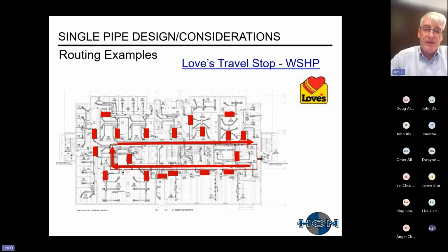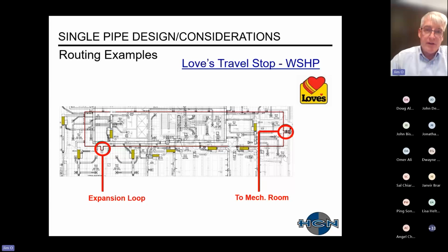On the right is a mechanical room, and then they have a piping main with a loop that runs in the center of the building. Those red rectangles are water source heat pumps. Each of those water source heat pumps would have a small branch pipe from that piping main in the center of the building. Just remember to include your expansion loops, et cetera. You still have to put those in, whether it's a single, 2 or 4 pipe system.